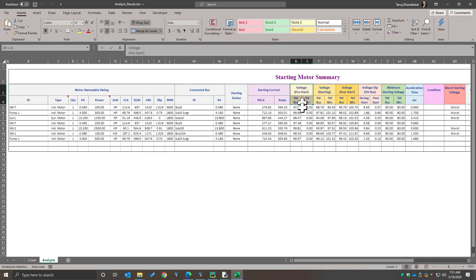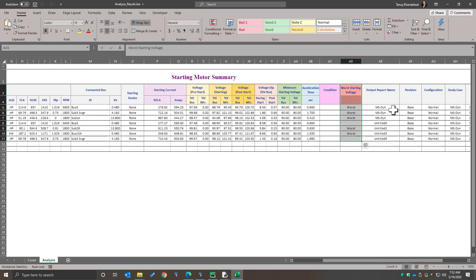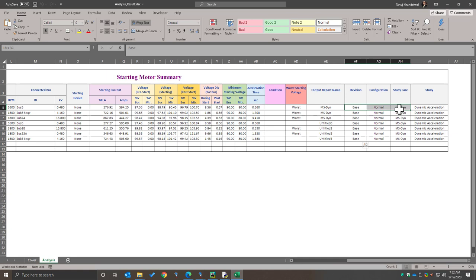The analyzer shows that we've looked at every single motor with the ability to start dynamically, evaluated the starting current based on results, looked at pre-start voltage, starting voltages, post-start voltages, voltage dip during acceleration, evaluation criteria, and acceleration time — giving us the worst case motor starting condition across all different cases. All these output reports correspond to every scenario that can exist for each machine. With Python scripting, if you have 500 machines and 20 scenarios, program automation can evaluate every single study case configuration across all machines and produce a worst case result in one shot.